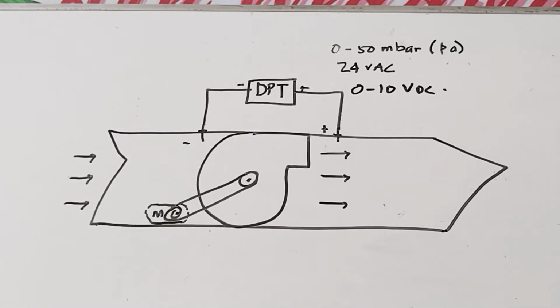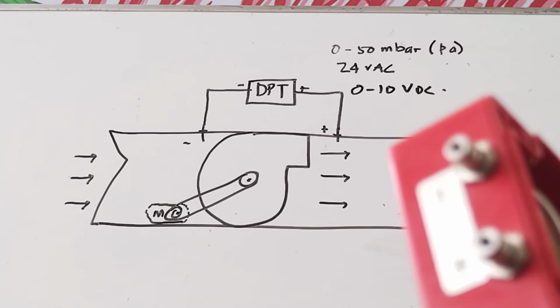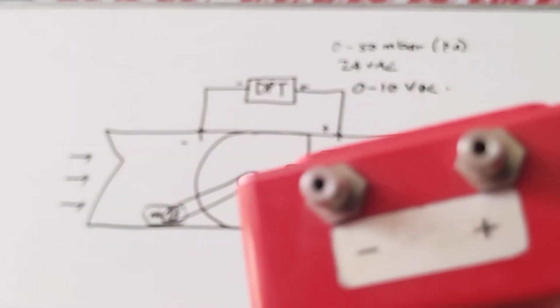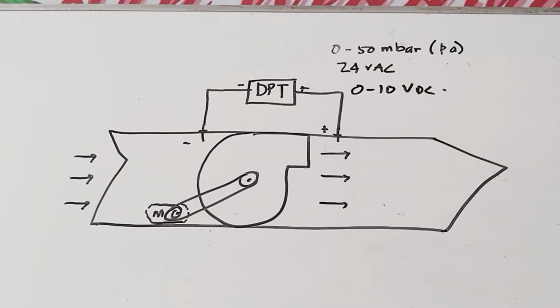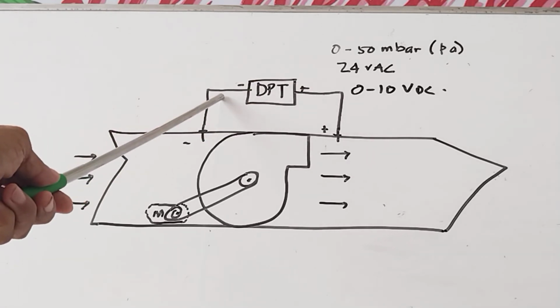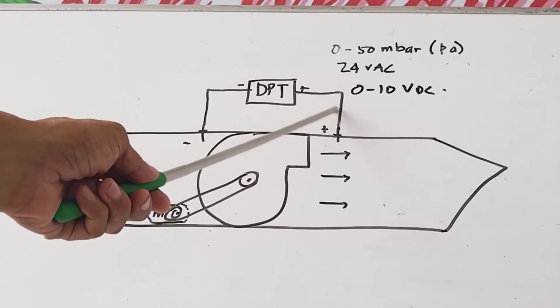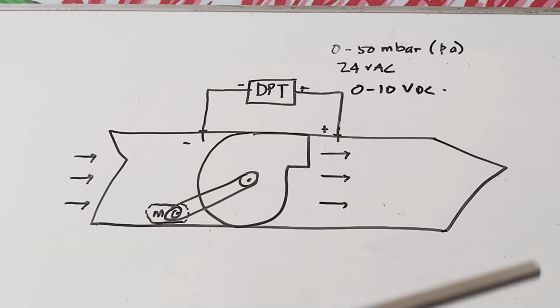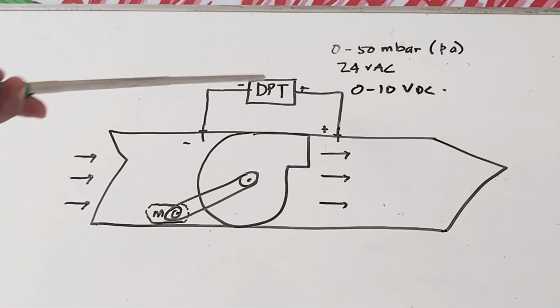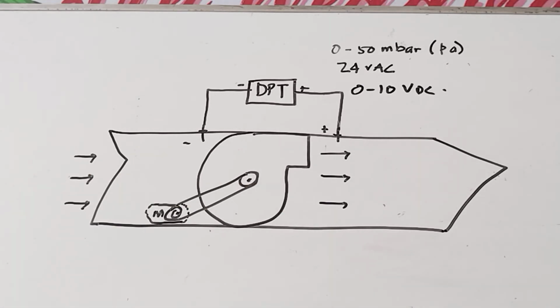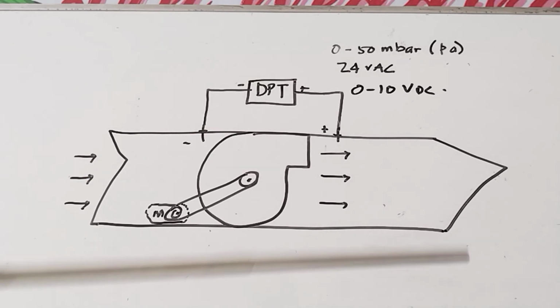Okay guys, so that is how you are going to install the differential pressure transmitter. Okay, so what I have, this one. Okay, so as you can see the probe. Okay, sorry, it is not very clear. Okay, so these are the two probes, plus and minus. Okay, so again, you will be using plastic tubing to connect the port. Okay, so the positive and the negative port, you need to use this plastic tubing. Okay, sometimes you can also use a copper tube. Okay, if you want to be more sturdy, because plastic will be easy to crack or kink. But if it is a copper tube, then it will be very sturdy.